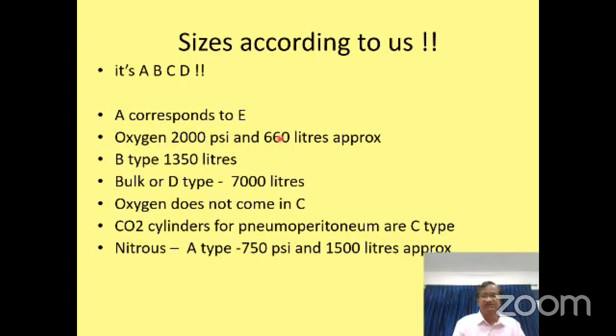Nitrous oxide A type may contain 750 psi, 1500 liters. Here oxygen is 2000, and nitrous is 750. Here it is 660, and this is 1500 liters. That is the A type cylinder of nitrous oxide. Now you can see this is the A type oxygen cylinder. Here you can see the valve. The valve is not bull nose like this. The valve has to be connected to the Boyle's machine to get oxygen. It cannot be opened and just give oxygen within the ward. So this is A type, this is B type, this is D type, and this is the carbon dioxide C type. A, B, C, and D. But C does not have oxygen.